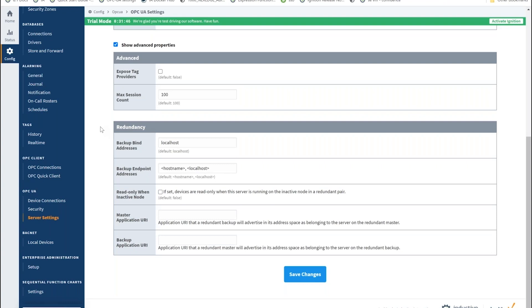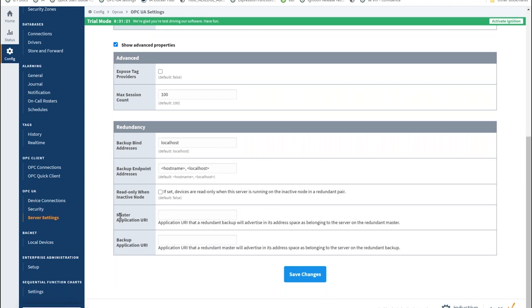If you have a client connecting into Ignition, you can use the standard failover between if one fails so you can go to the next one. Some of these settings are related to that, but it doesn't actually publish out those redundancy tags as of right now. I just wanted to make that clear. We are looking at adding that piece in the future, but I didn't want to lead anybody in the wrong direction here. Kevin, I believe that was released in 8.1.10, so I think we at this point should have support for both server and client side just overall for the OPC UA, which is definitely good.